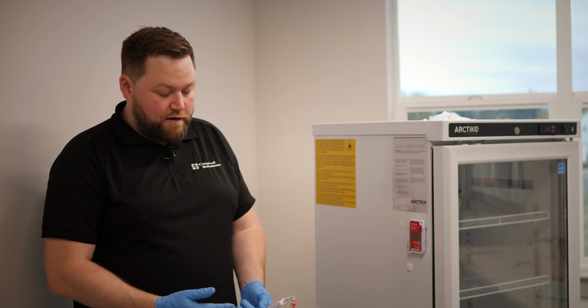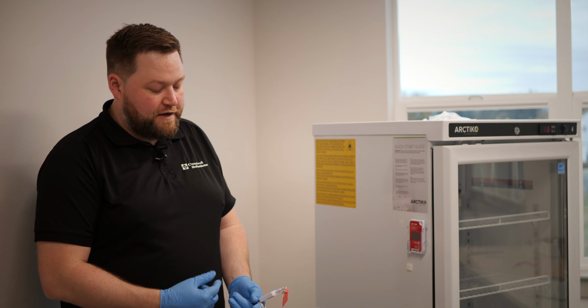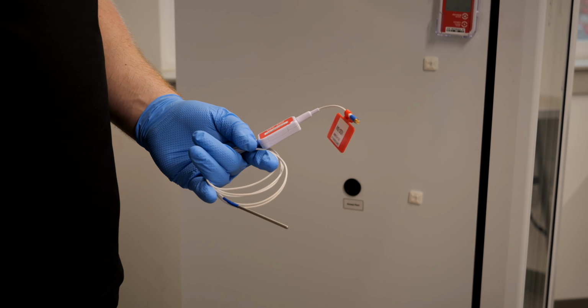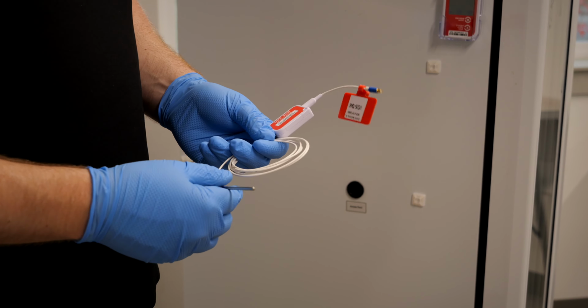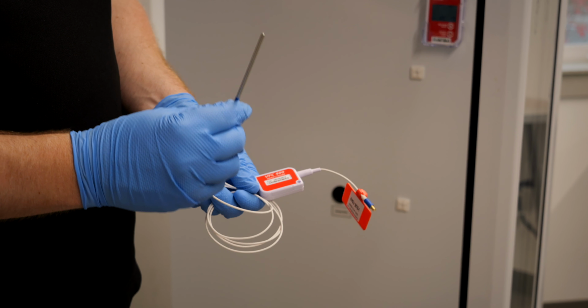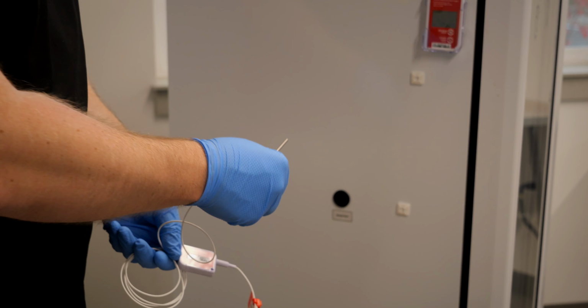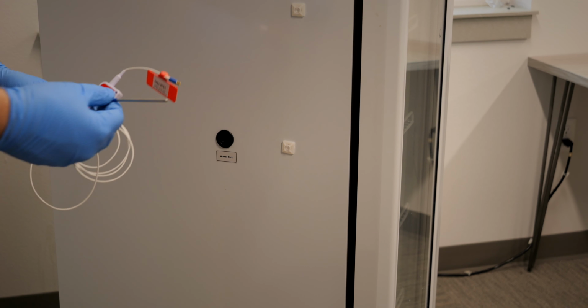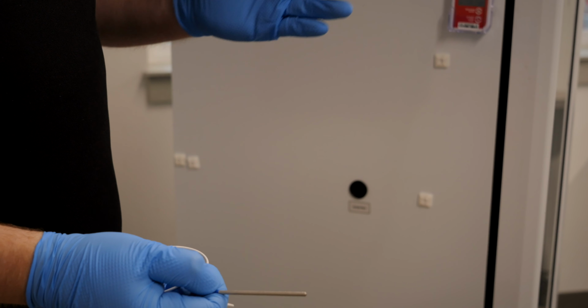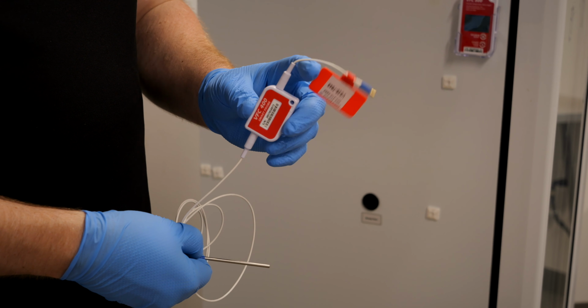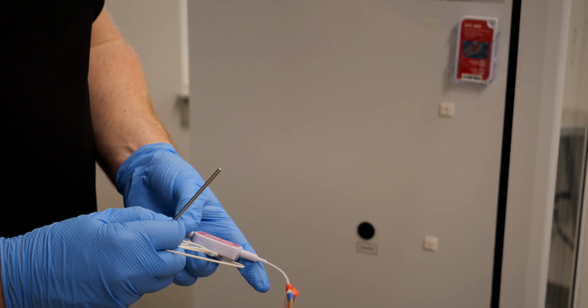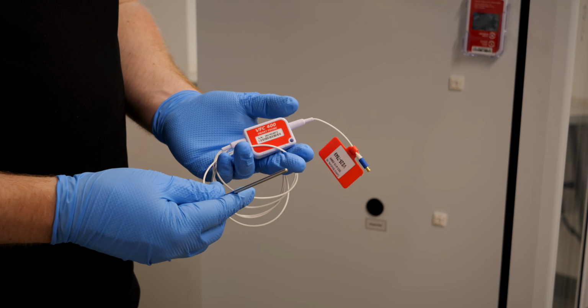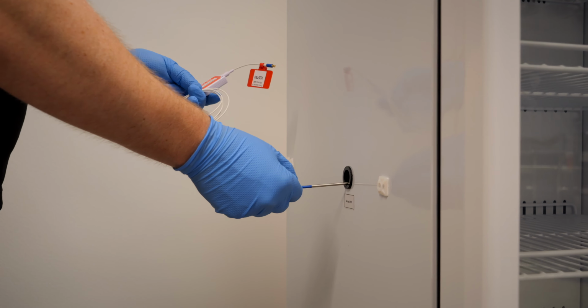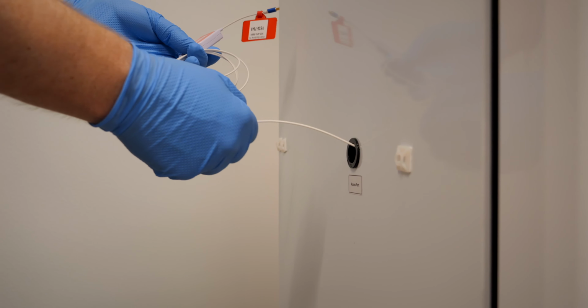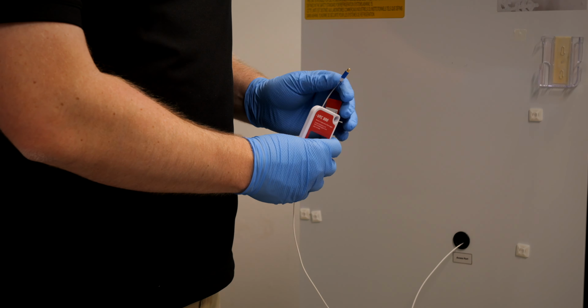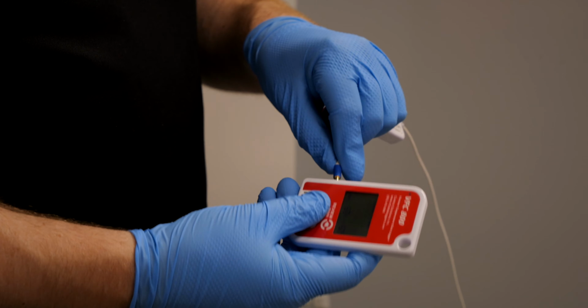Now that we have our data logger and wall mount bracket placed on the refrigerator, it's time to install and route our probe cable. It is important to note that when installing our temperature probe, we always want to install it probe-first into the interior cabinet of the refrigerator. We're always installing our probe from the outside of the unit into the inside because the connector will not fit through most fridge pass-throughs. That's a tip to make it a little bit easier, and that's also why during the unboxing we took off the cap and seal, to allow us to fit this probe through that pass-through. I'm simply going to connect the probe to our logger.